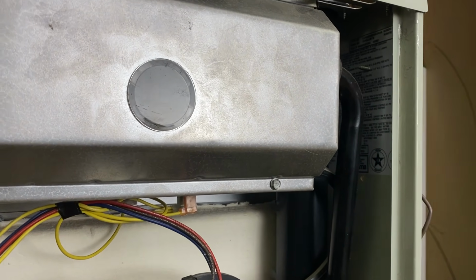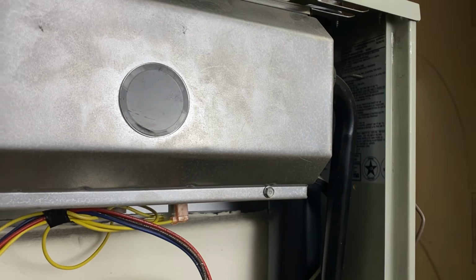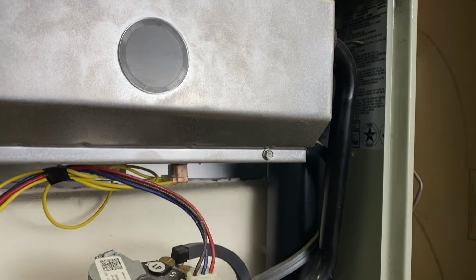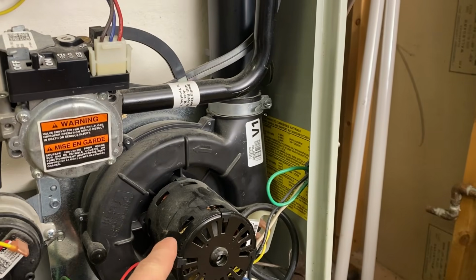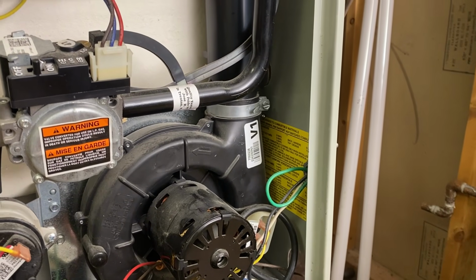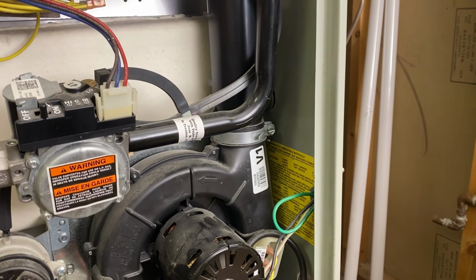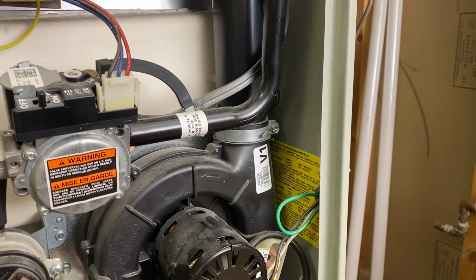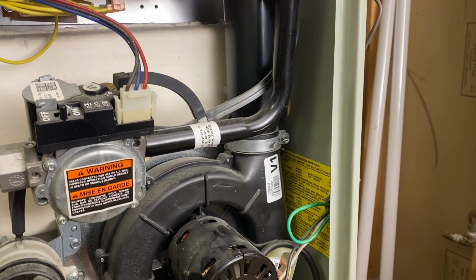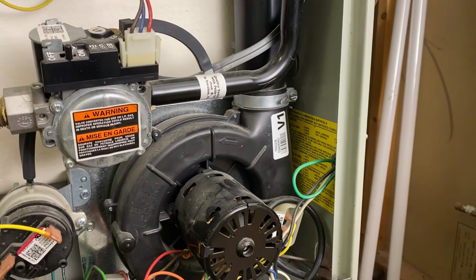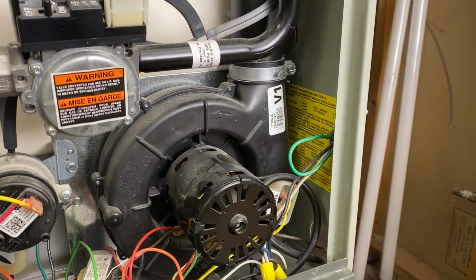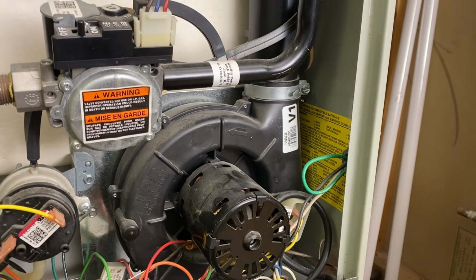So no hot surface igniter means no flame, and the flame sensor didn't sense any flame, and so the gas valve shut off. Now this will run for another 30 seconds or a minute or so to clear out any gas that got sprayed into the heat exchanger, make sure that's all cleared out of there, and then it'll try again. It'll keep trying, and that's what ours has been doing. And then eventually it gives up and shuts off, and then the trouble code will start to flash.